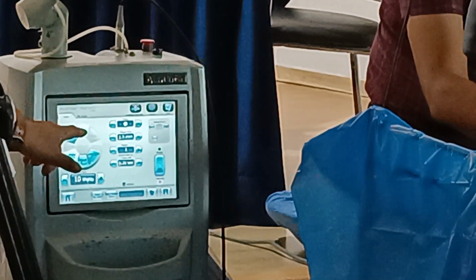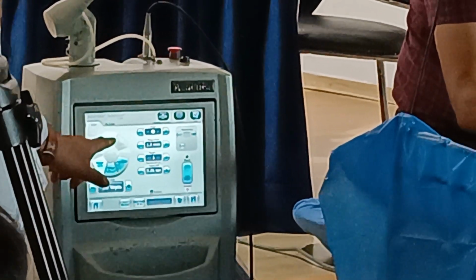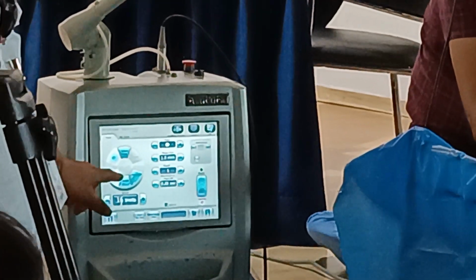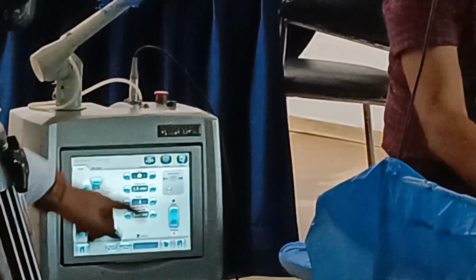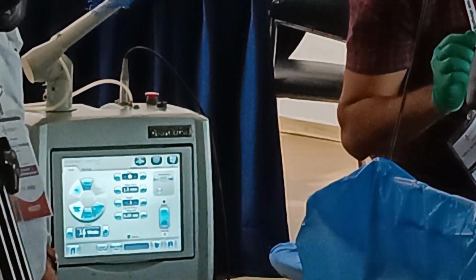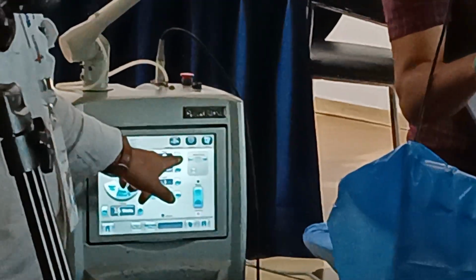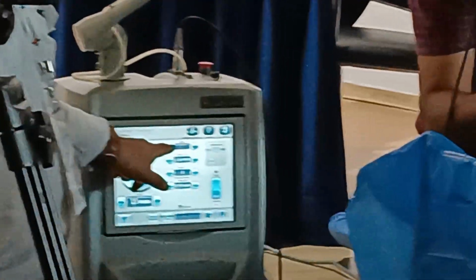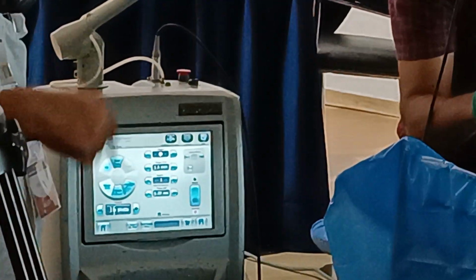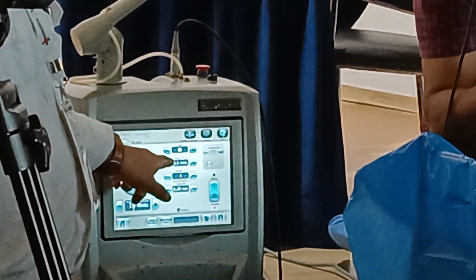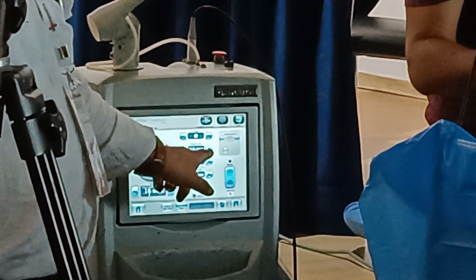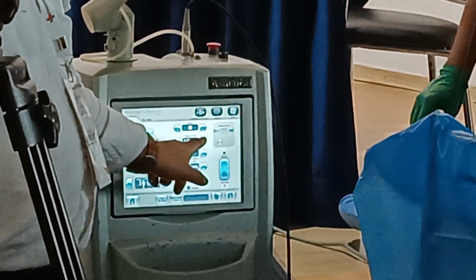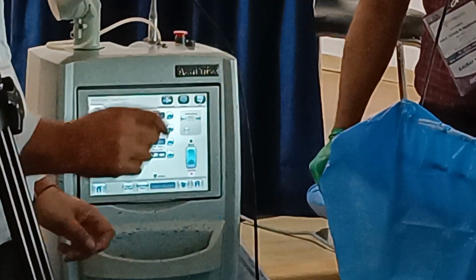Especially with a continuous beam, sometimes if you want to work very fast, if you are on the papilloma, you want to work very fast and it need not be very precise, then you can go on to a continuous mode. Here you can control the shape, the different shapes. This is curve to one side, curve to the other side, straight, and circle for fulguration. This is the size. You can start from 0.5, 1 and go higher and higher, the beam size will be bigger.